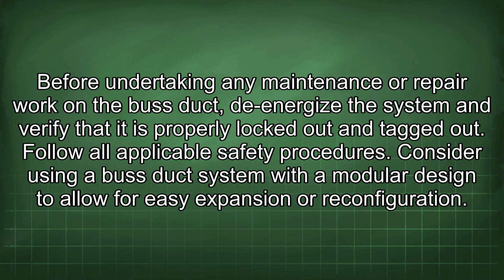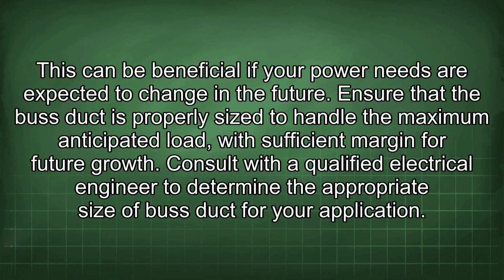Before undertaking any maintenance or repair work on the bus duct, de-energize the system and verify that it is properly locked out and tagged out. Follow all applicable safety procedures. Consider using a bus duct system with a modular design to allow for easy expansion or reconfiguration. This can be beneficial if your power needs are expected to change in the future.